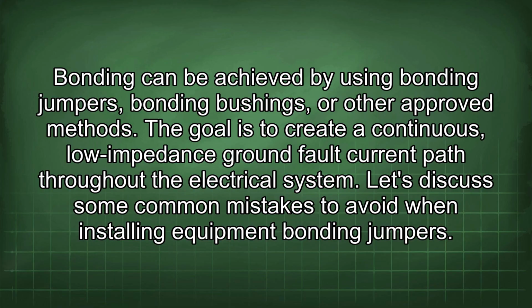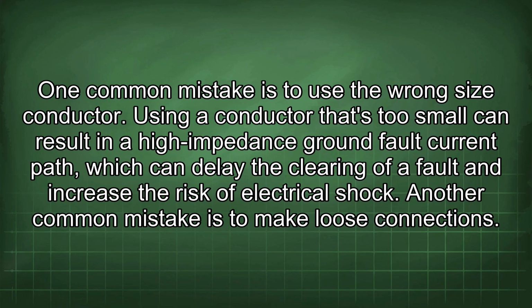Let's discuss some common mistakes to avoid when installing equipment bonding jumpers. One common mistake is to use the wrong size conductor. Using a conductor that's too small can result in a high impedance ground fault current path, which can delay the clearing of a fault and increase the risk of electrical shock.